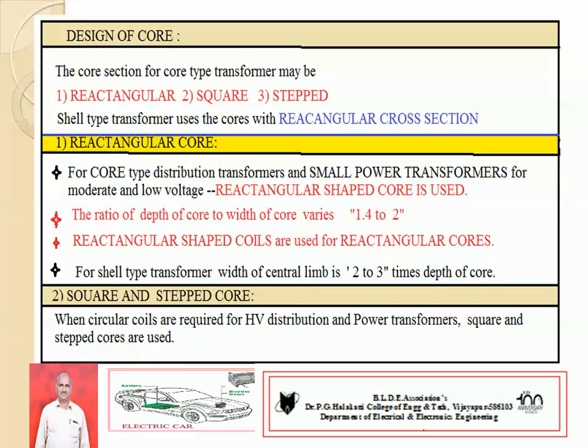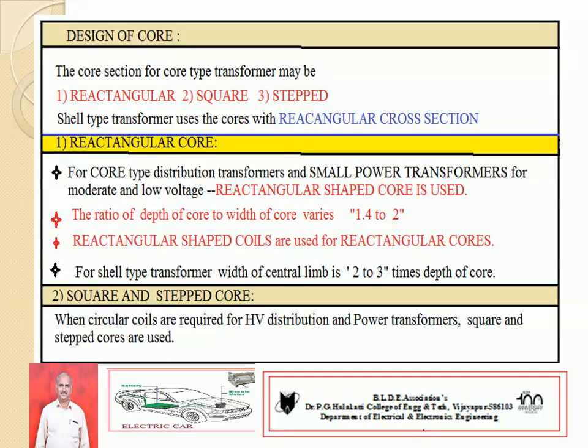The ratio of depth of core to width of core varies between 1.4 to 2, and rectangular shaped coils are used for rectangular cores. If the core section is rectangular, then rectangular shaped coils are also used. For shell type of transformer, the width of the center limb also varies from 2 to 3 times the depth of core.